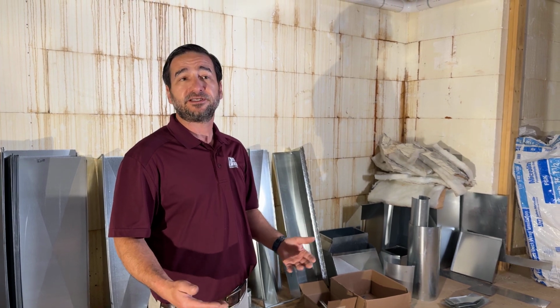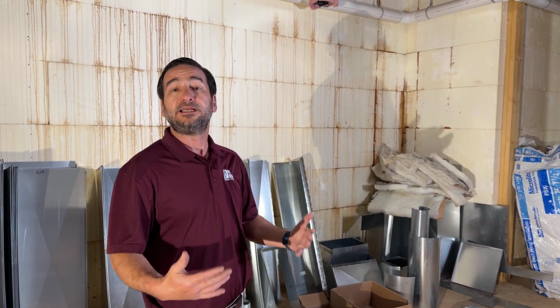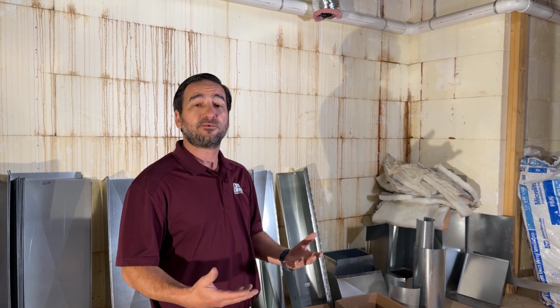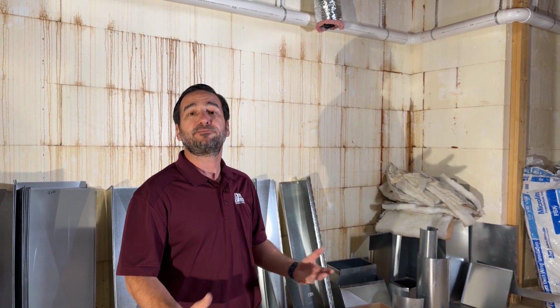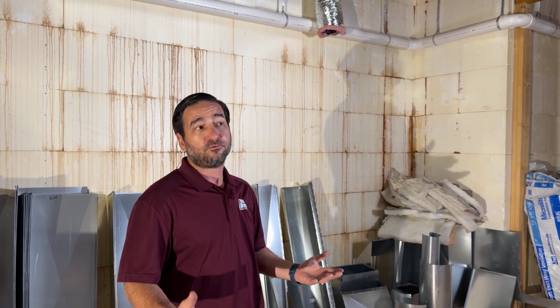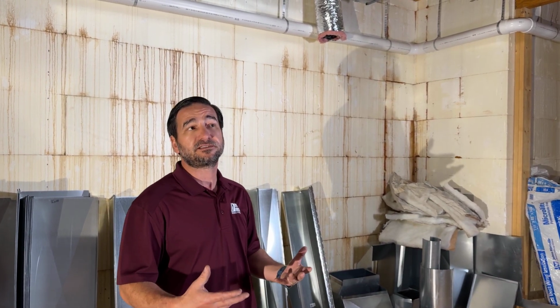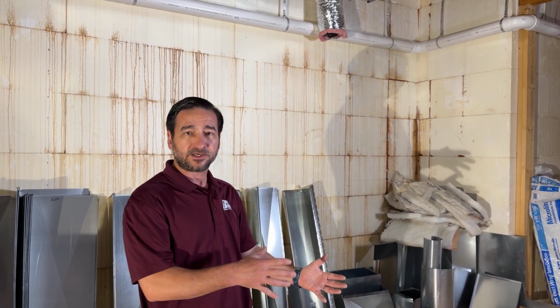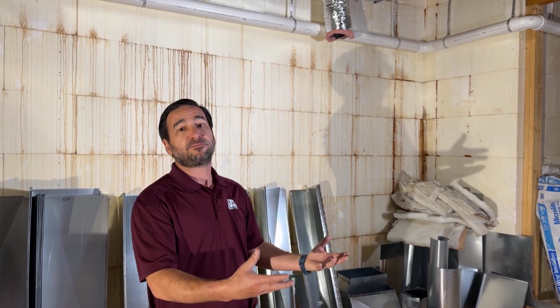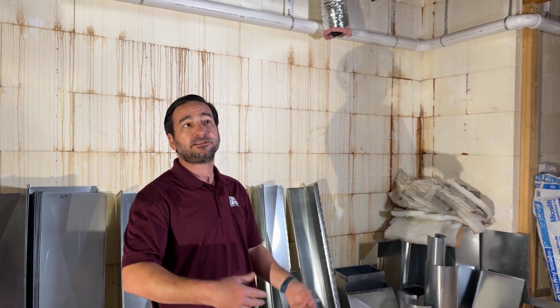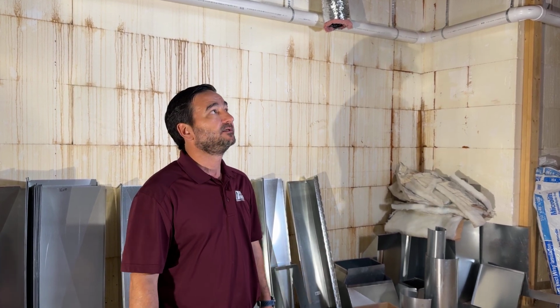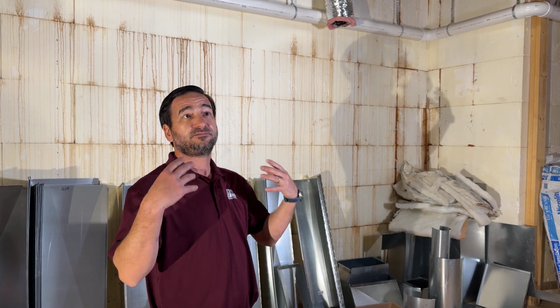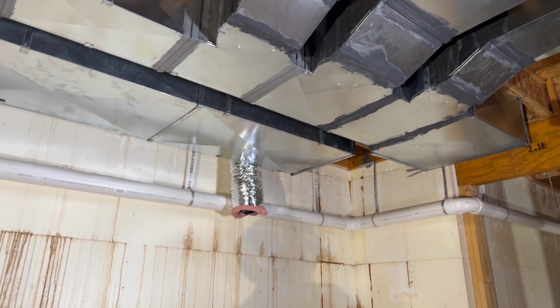So in this particular house, it's ICF. An ICF house is inherently very efficient. It doesn't need very much air conditioning or heating to be able to condition it. But the problem with that is if these homeowners decide to have a big party and they load it full of people, they want to be able to air condition it. So with a zone system, it gives you the ability to shift the energy where you need it. So in this configuration, if they're having a party, they can turn that area down, but they're not necessarily overcooling the bedroom or the basement to accommodate that extra need. So like I say, just trunk and branch duct system, sealed up, and five zone system.